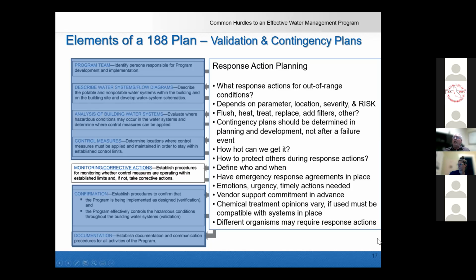There's a lot of debate over hyperchlorination. That's something that has historically been very popular. Most facilities have dealt with it, not all now, it's changing, but chlorine has been very commonly used as a general disinfectant from the municipalities. We like to throw a lot of chlorine at stuff, but we're finding chlorine is really good at killing the bacteria floating around in the water, but not as effective at penetrating into the biofilms where those things are growing.